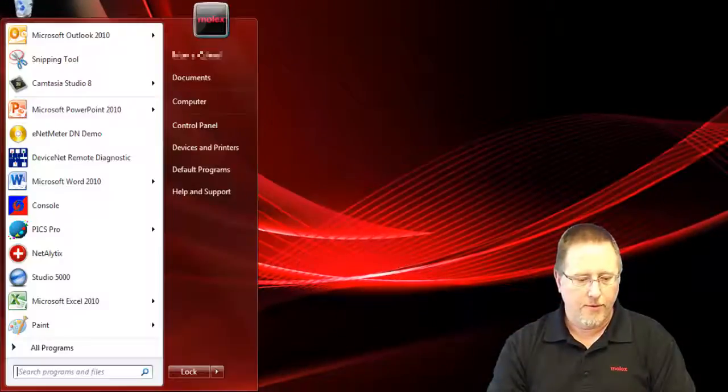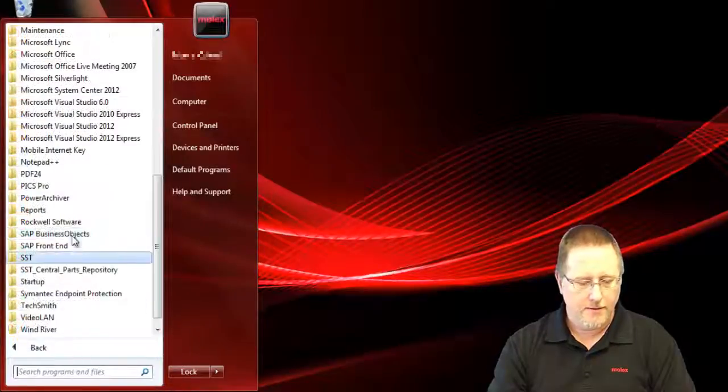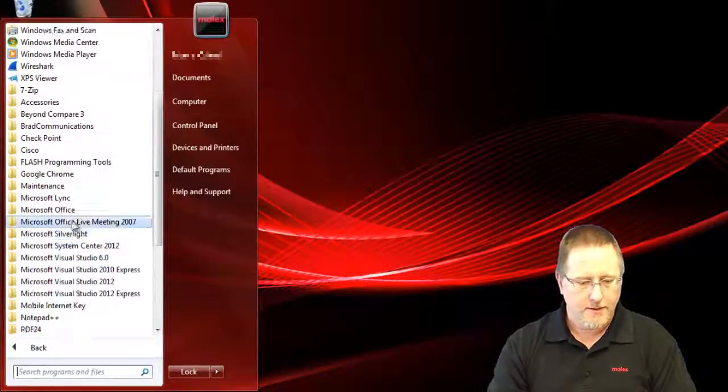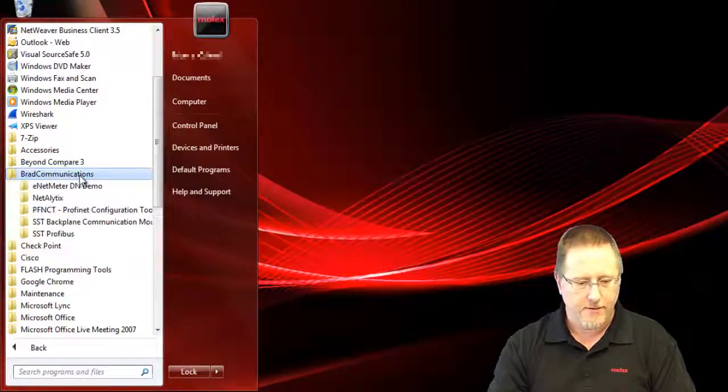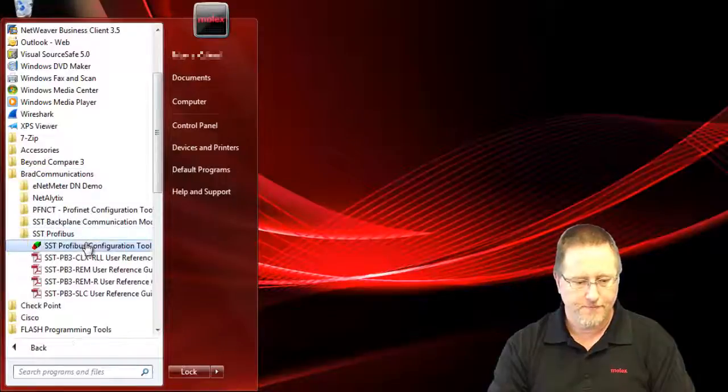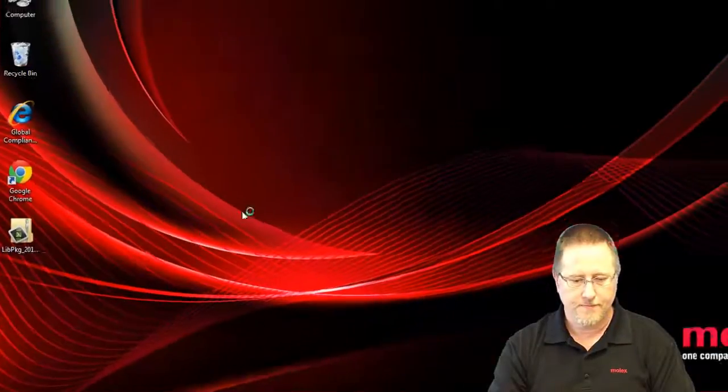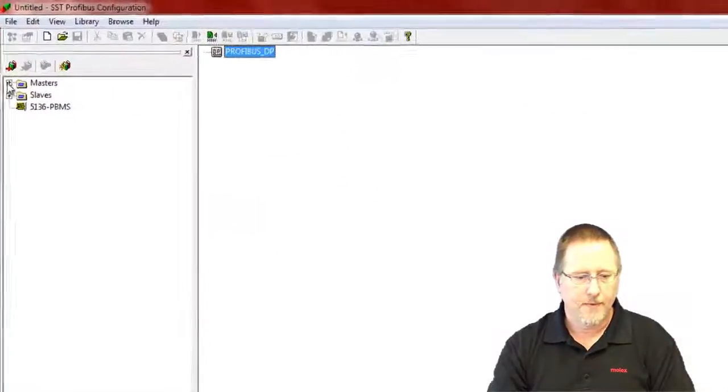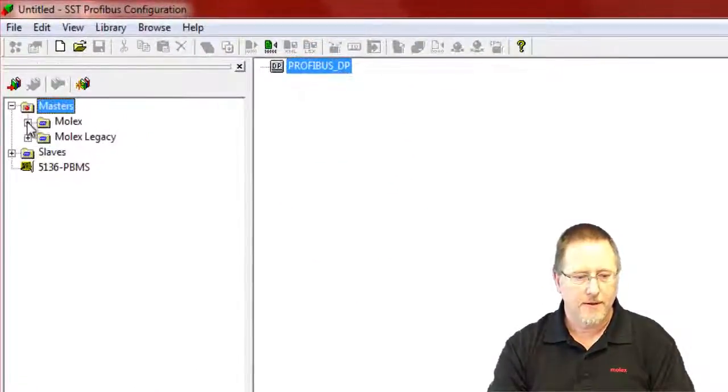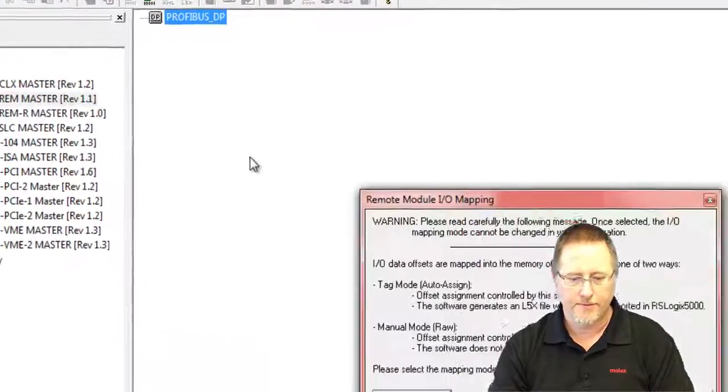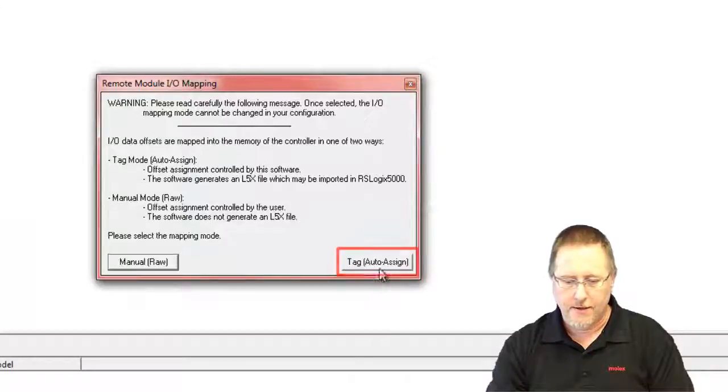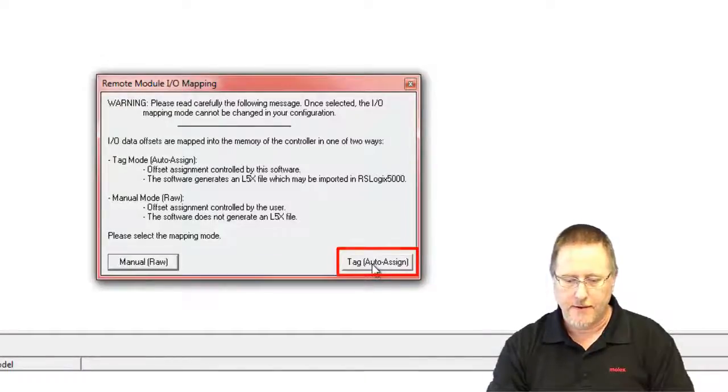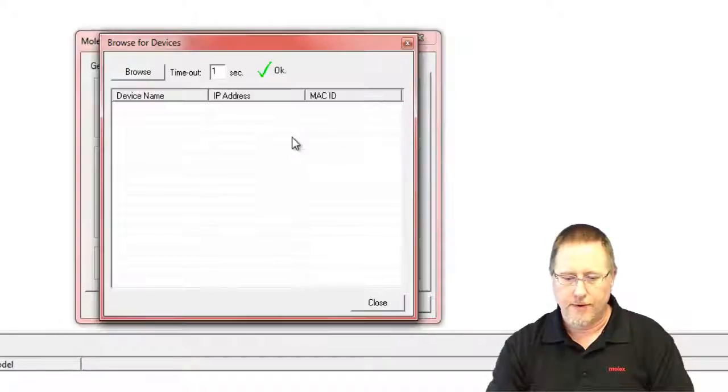Now we want to open the SST Profibus configuration software. Expand our list of masters. We'll grab the REM module and we want to select the auto assign here because we're going to use the L5X file in our logics, and we're going to browse for devices.